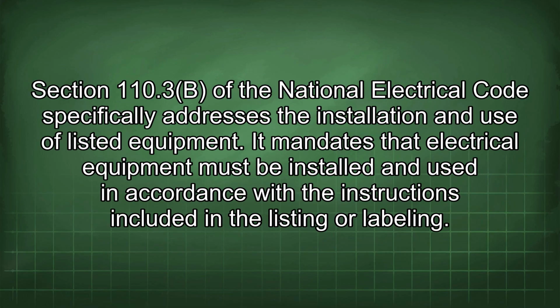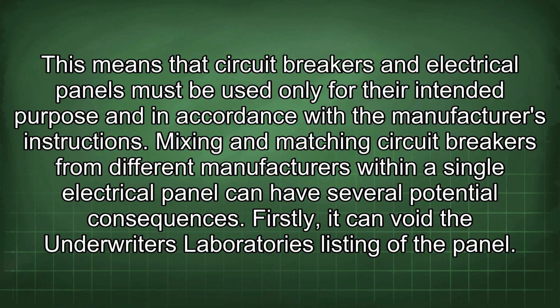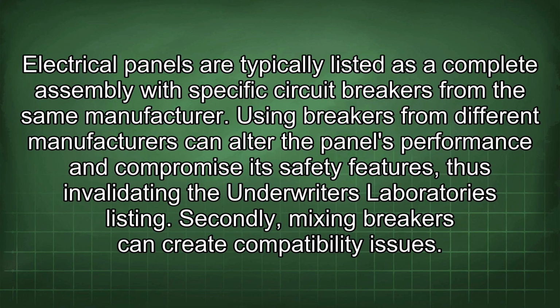Section 110.3(B) of the National Electrical Code specifically addresses the installation and use of listed equipment. It mandates that electrical equipment must be installed and used in accordance with the instructions included in a listing or labeling. This means that circuit breakers and electrical panels must be used only for their intended purpose and in accordance with the manufacturer's instructions. Mixing and matching circuit breakers from different manufacturers within a single electrical panel can have several potential consequences. Firstly, it can void the Underwriters Laboratories listing of the panel. Electrical panels are typically listed as a complete assembly with specific circuit breakers from the same manufacturer.